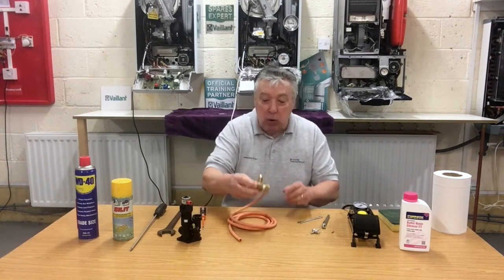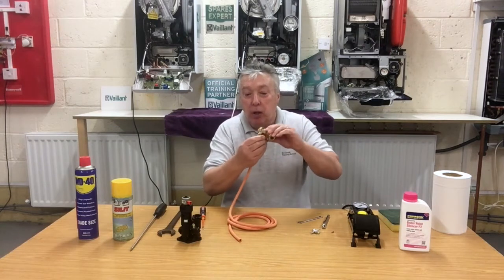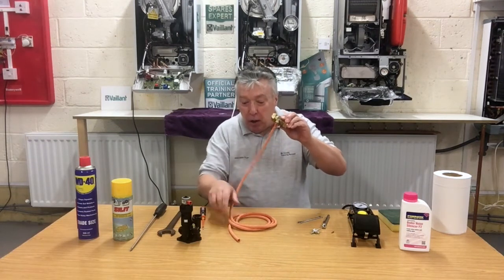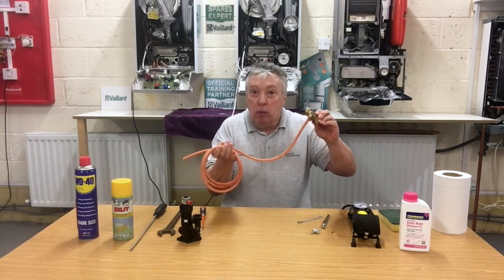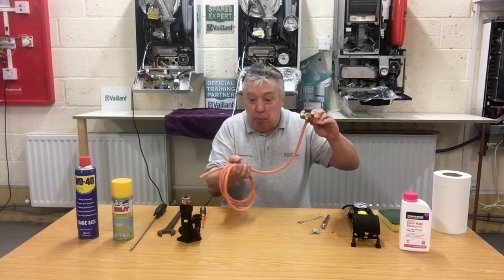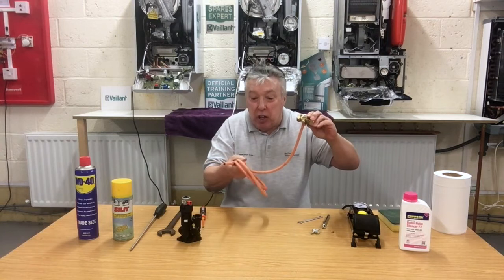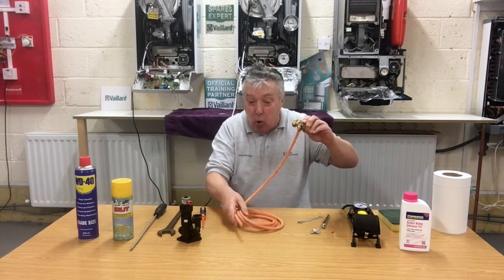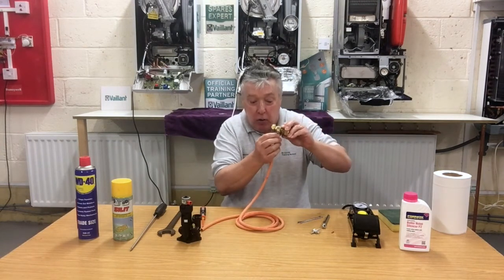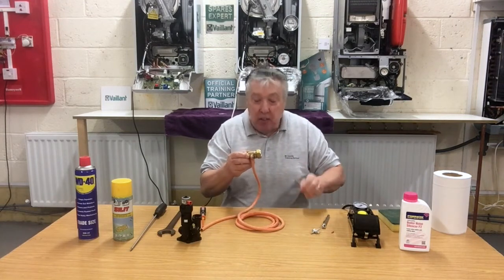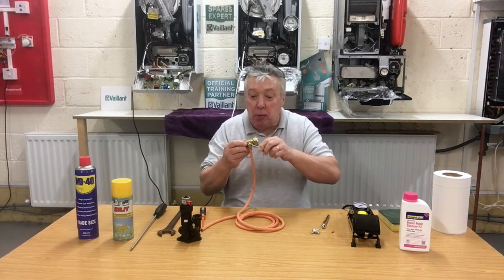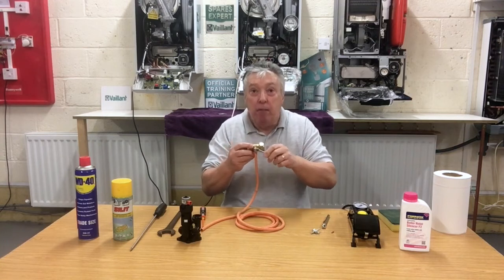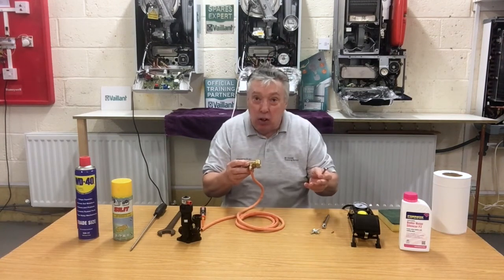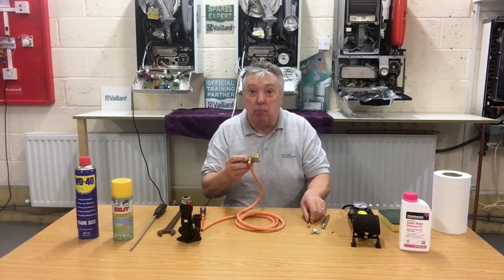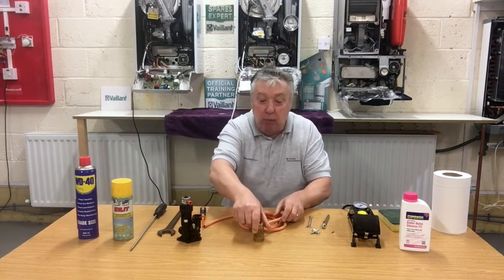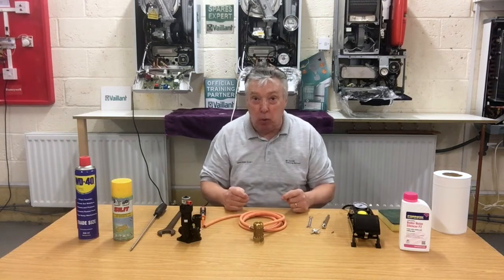When we drain down, we've always got a drain off point here, and I'm using an old water gauge hose since we use digital these days, but these are handy and long, so they slide on perfectly. With a 7mm spanner we simply undo the drain off, first on the return and then on the flow side, to remove as much water as we can so we don't flood the boiler or the worktop we're working on.